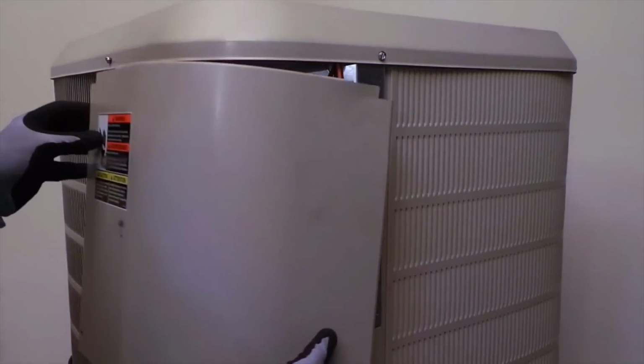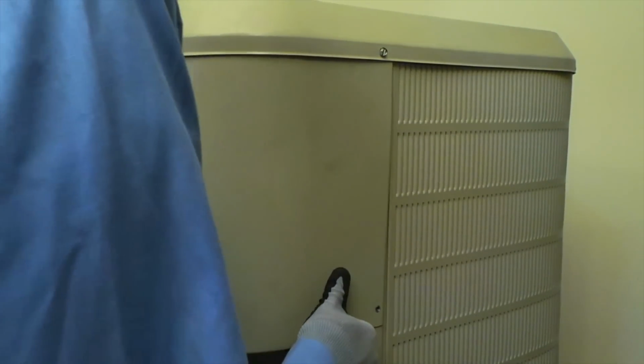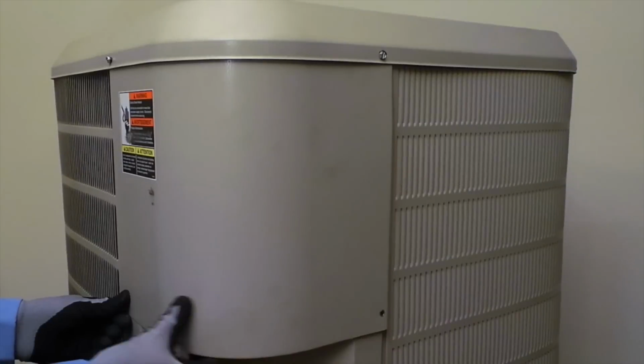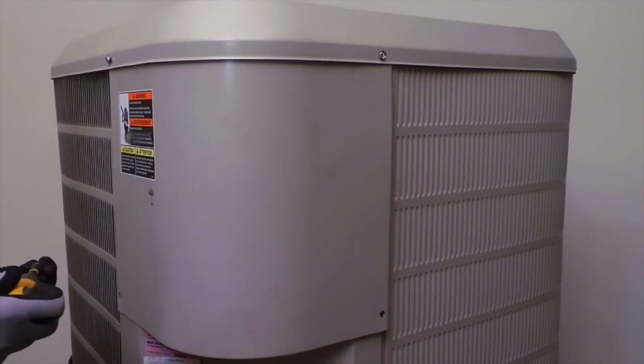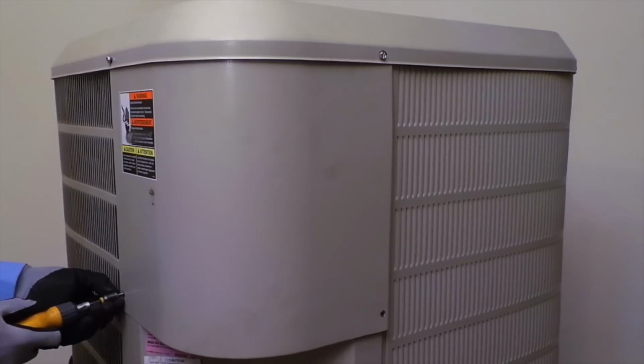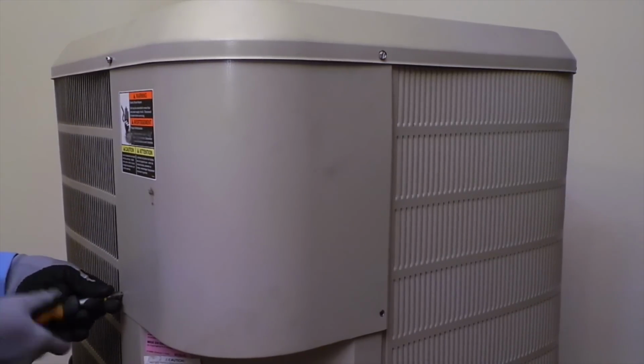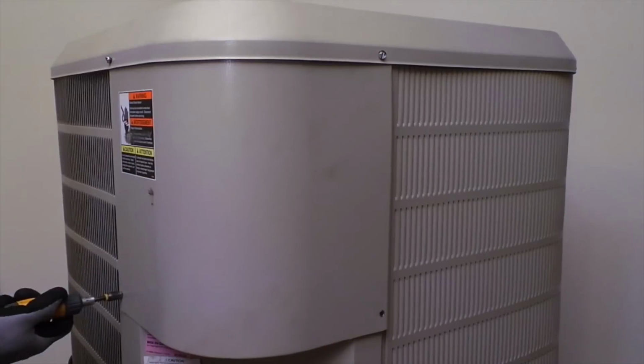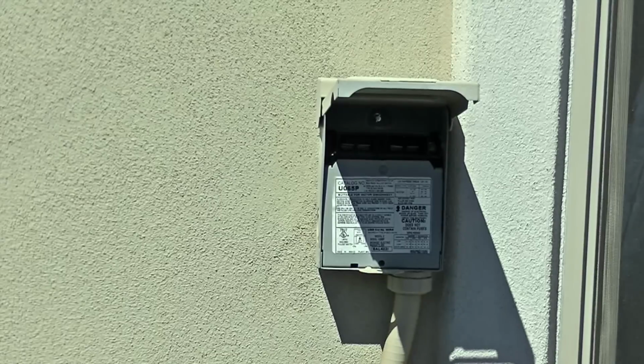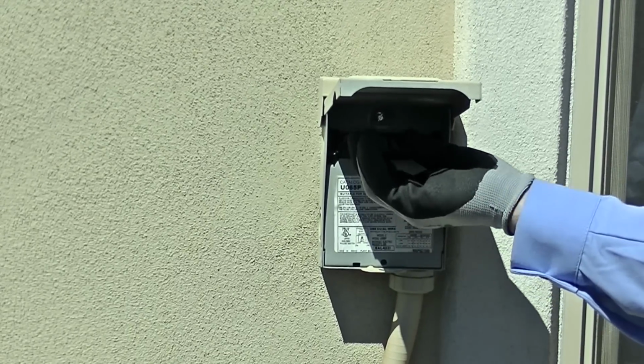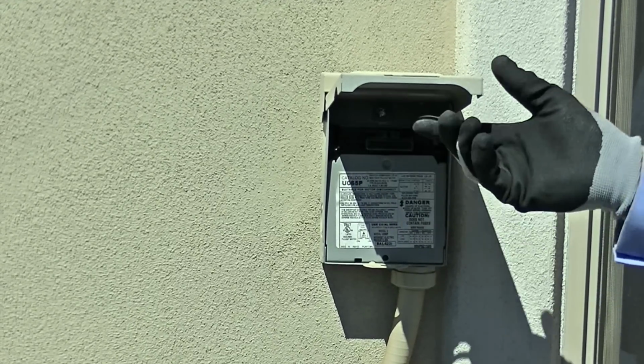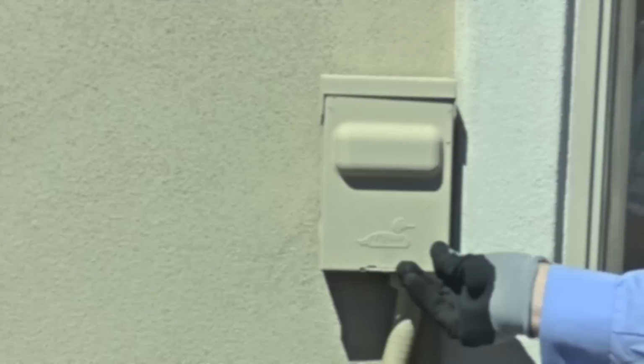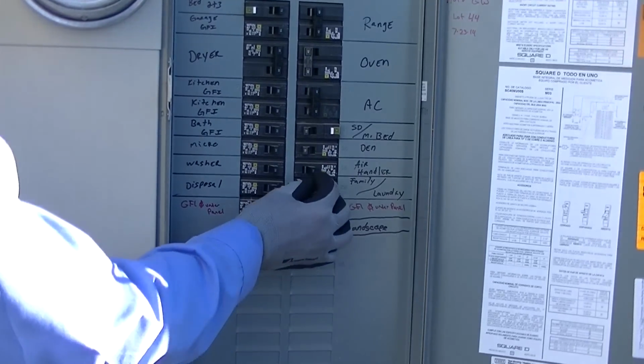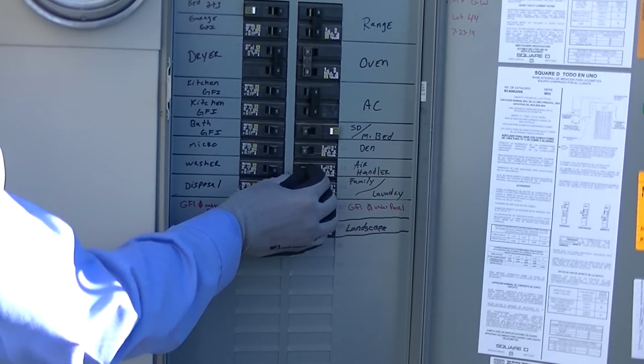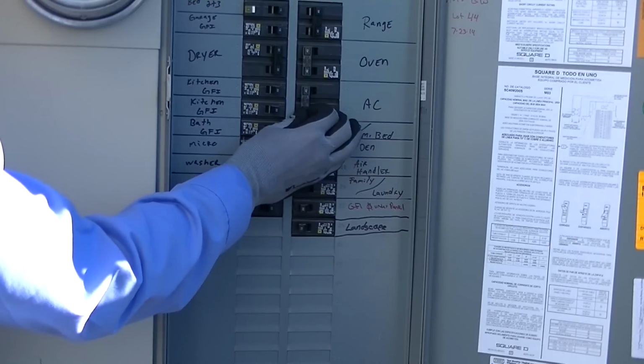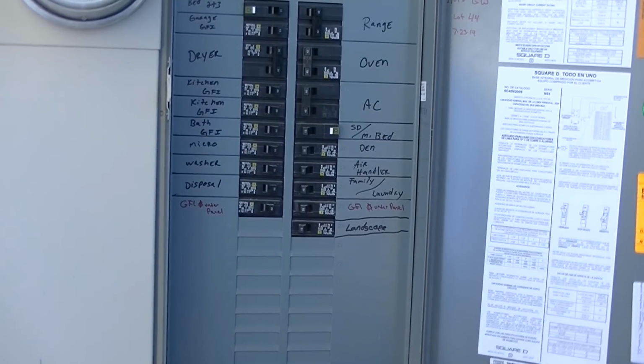Now it's time to put our control panel back in place, sliding it up and in. Then aligning our screw holes, we reinsert our screws using the same nut driver that we used previously, putting both securing screws, one in each side of the control panel. Now we will reinsert our disconnect block back into our disconnect box, closing the panel. Going back out to the circuit breaker panel, we turn the circuit breaker for the furnace or air handler and the circuit breaker for the condenser back on, and we're ready for operation.